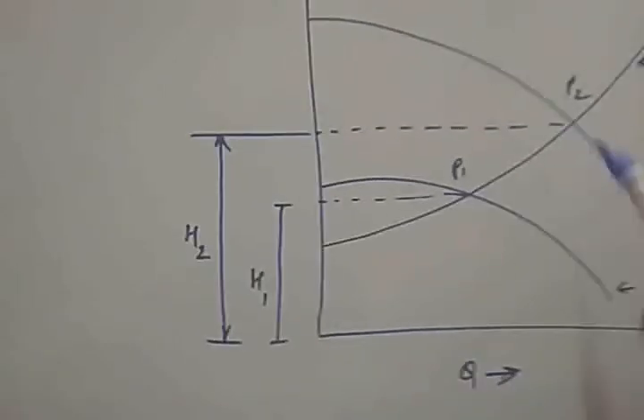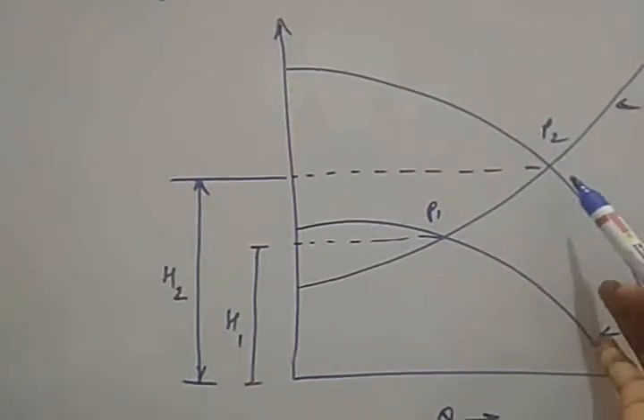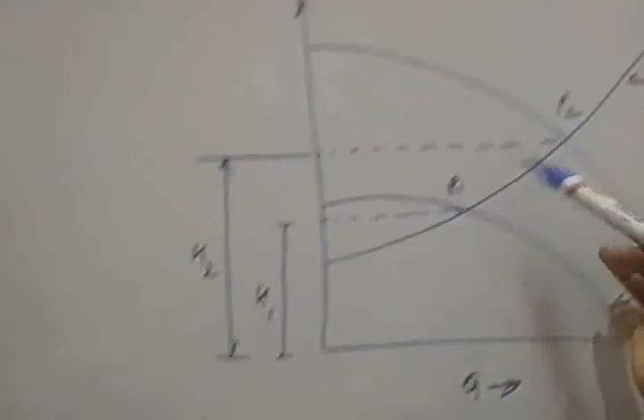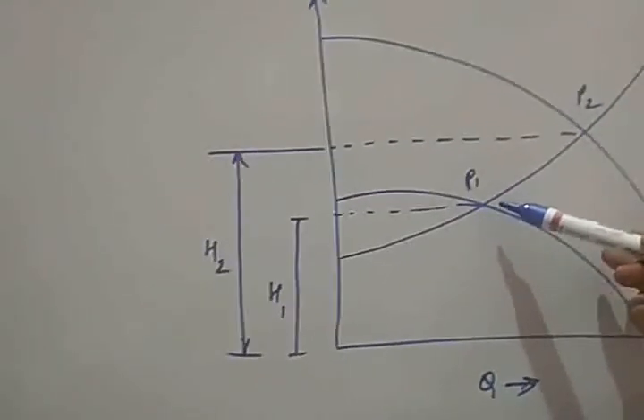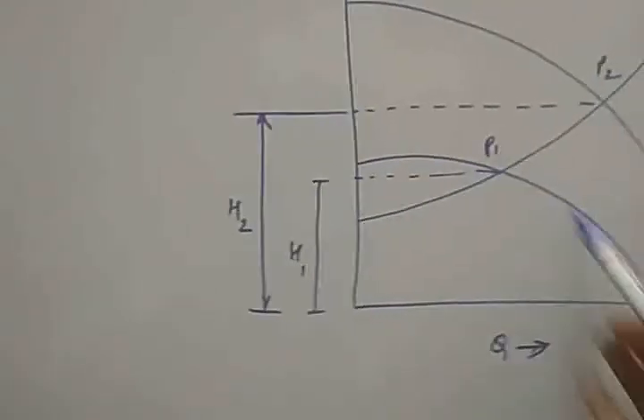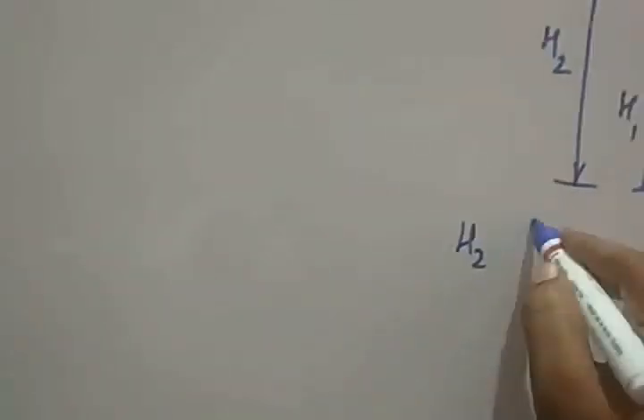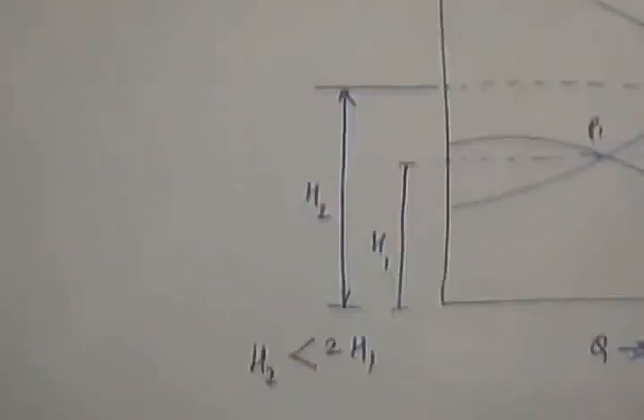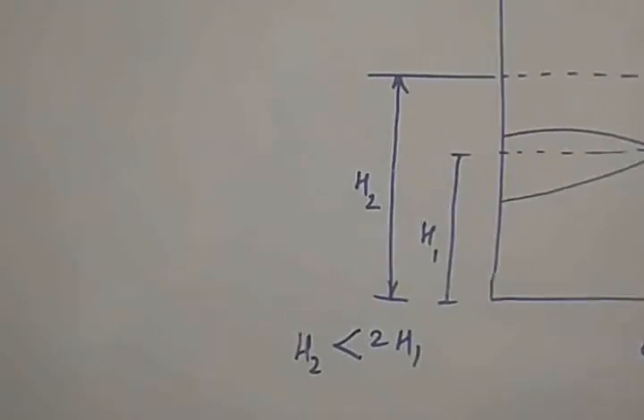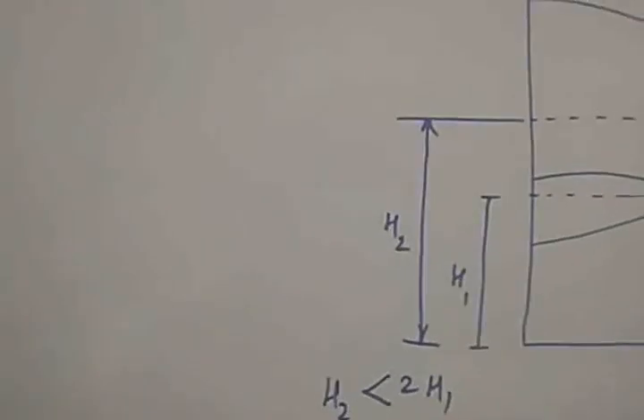The point of intersection of the combined total head-discharge characteristics and the system head curve shows that P2 is larger than P1. H1 is with respect to P1 and H2 is with respect to P2. We can see that H2 is less than 2H1 — so though two pumps are used, the head will not be double. A particular combination of pumps needs to be selected accordingly.